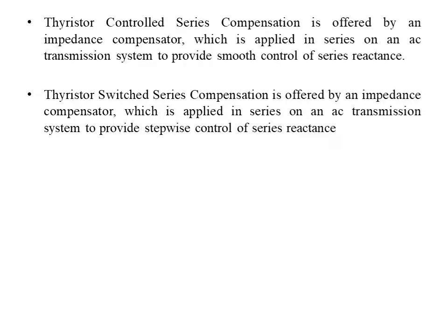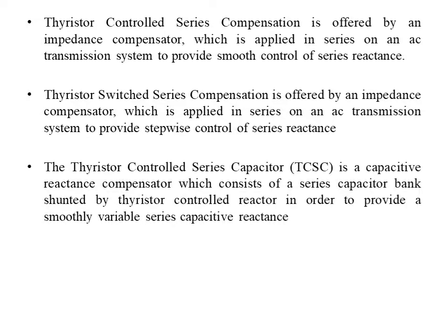Thyristor switched series compensation is offered by an impedance compensator which is applied in series on the AC transmission system to provide stepwise control of series reactance. Thyristor controlled series capacitor is a capacitive reactance compensator which consists of a series capacitor bank shunted by a thyristor controlled reactor in order to provide smoothly variable series capacitive reactance.